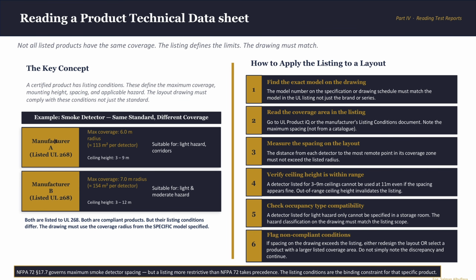So if you take manufacturer A's product and install it in a space with a 10 meter ceiling, that listing is violated. The product is now unlisted for that application. And here's the part most people miss. Even if the spacing looks fine on the drawing or layout, even if NFPA 72 is satisfied, the listing condition overrides it. The listing is the binding constraint for that specific product. So again, basically two products, same standard, different limits. The layout must match the specific product specified, not just the brand, not just the series, the exact model, the exact listing conditions.